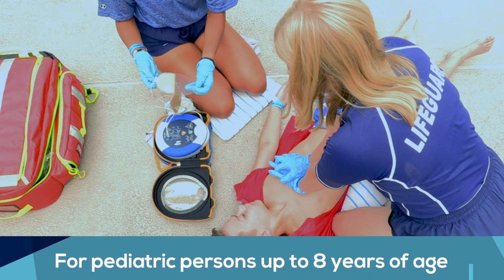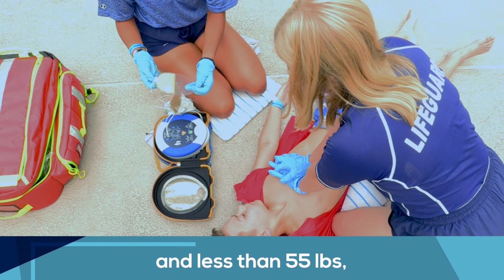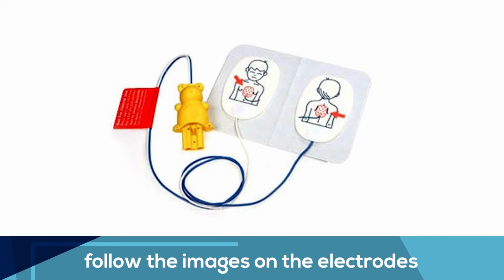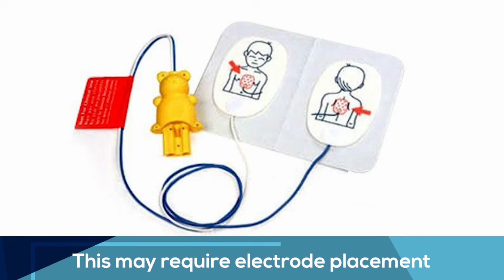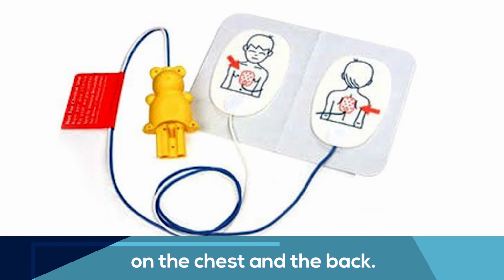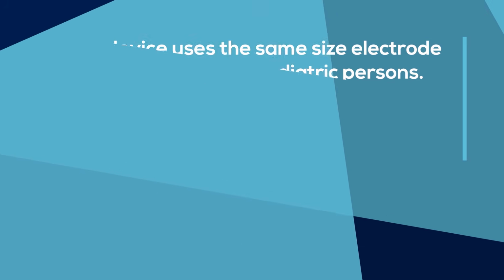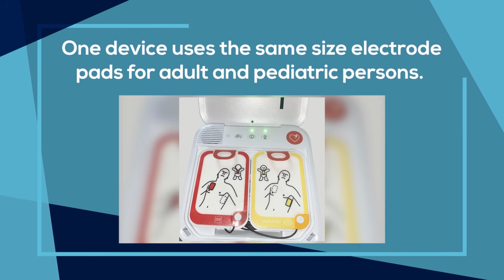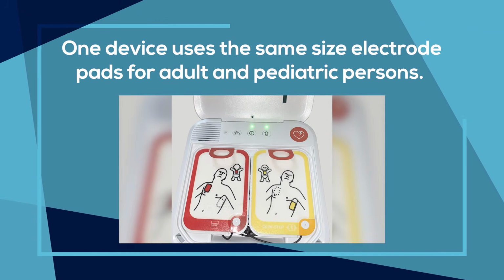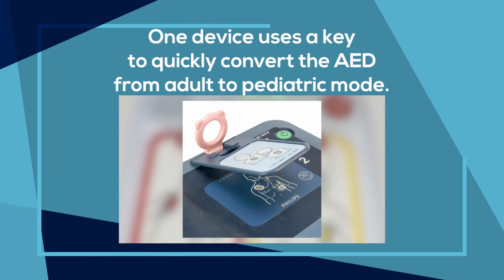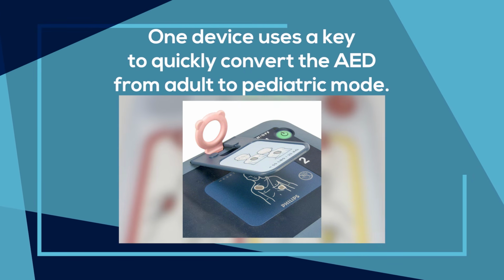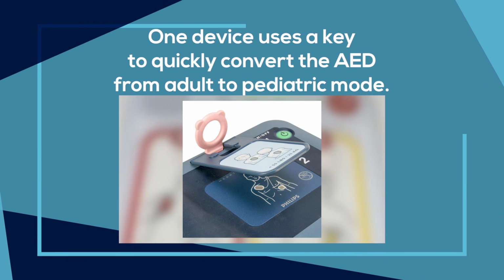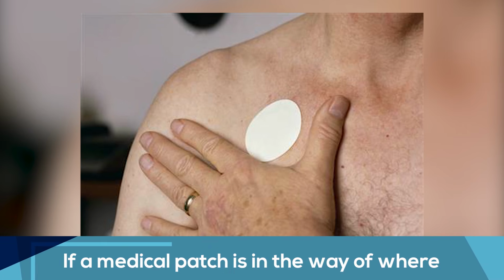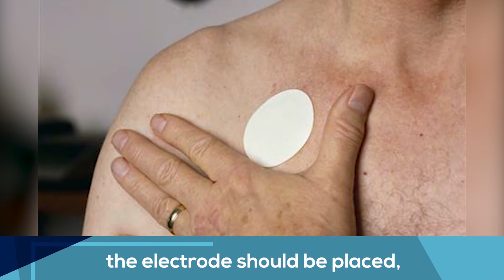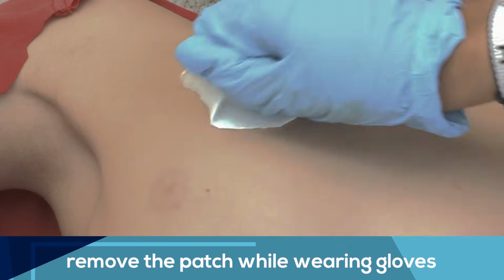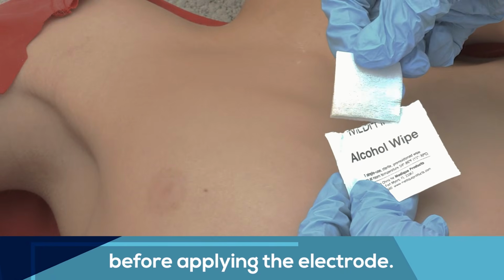For pediatric persons up to 8 years of age and less than 55 pounds, follow the images on the electrodes for proper placement. This may require electrode placement on the chest and the back. One device uses the same size electrode pads for adult and pediatric persons. One device uses a key to quickly convert the AED from adult to pediatric mode. If a medical patch is in the way of where the electrode should be placed, remove the patch while wearing gloves and wipe down the skin before applying the electrode.